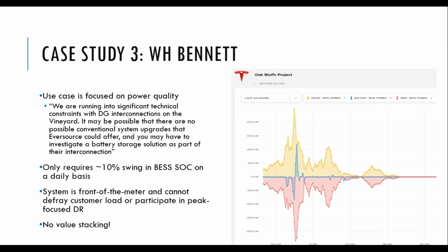So this battery is given a signal by Eversource as to how to mitigate that voltage flicker, but this only requires at most a 10% swing in the battery state of charge on any given day. Because the system is front of the meter with respect to any customer load, it can't defray customer load for demand charge purposes or participate in peak focused customer demand response programs. Fundamentally that means there really isn't any value stacking in this case. This facility is being used solely to defray this voltage flicker concern, and it's doing so very successfully, and it unlocked the value associated with the PV for this customer.